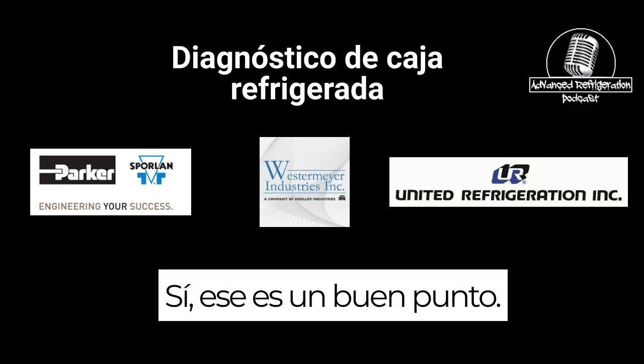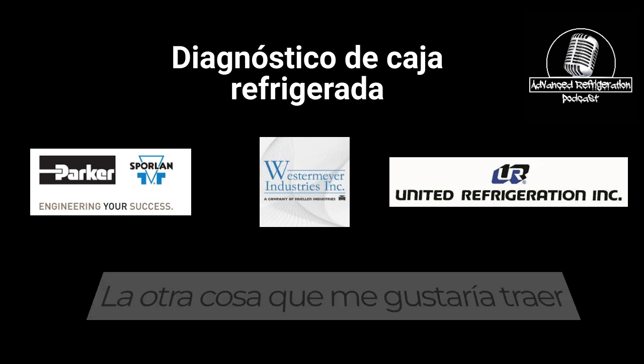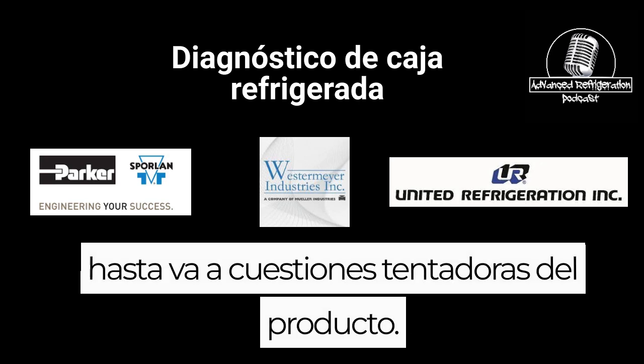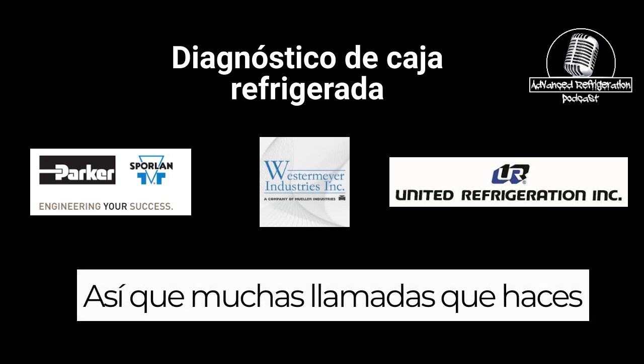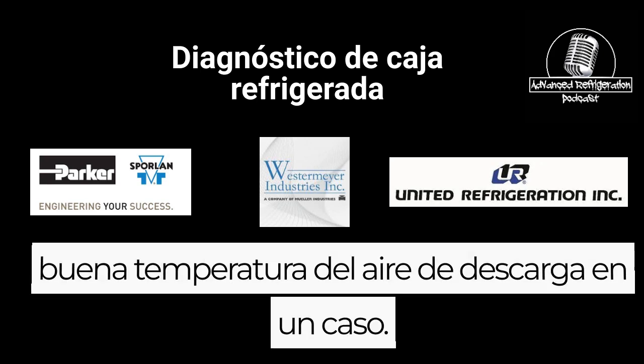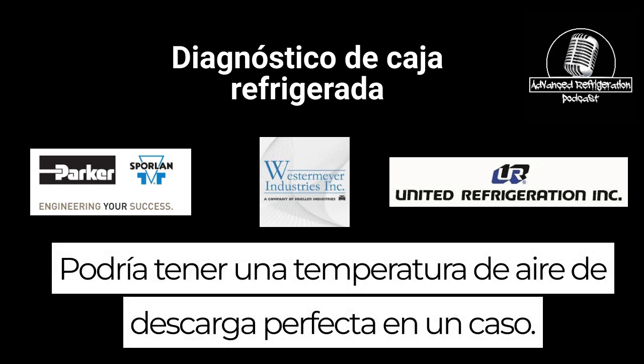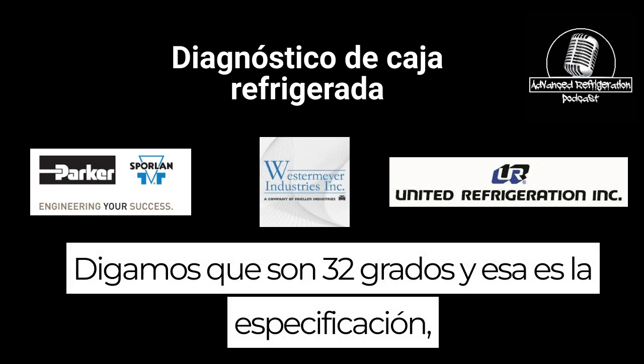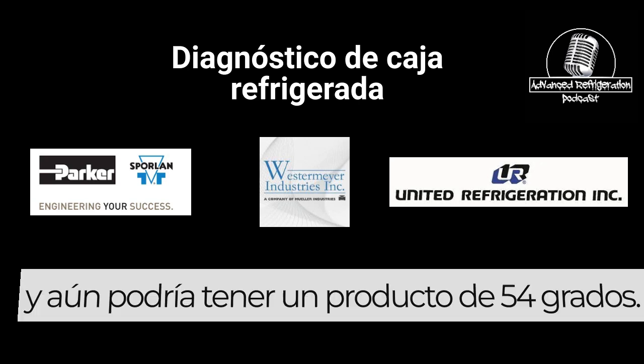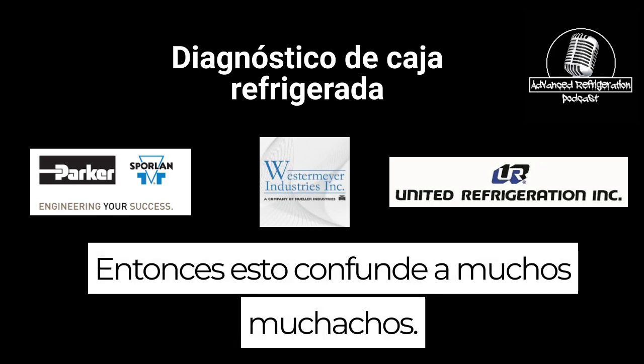Yeah, that's a good point. And the other thing I would like to bring up is product temp issues. A lot of calls, you could have perfect discharge air temp in a case. Say it's 32 degrees and that's the spec, and you could still have 54-degree product. So this messes up a lot of guys.